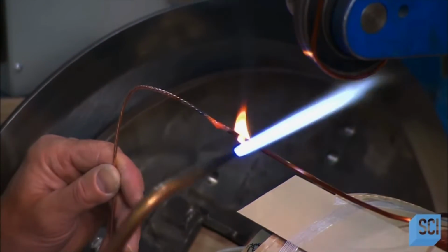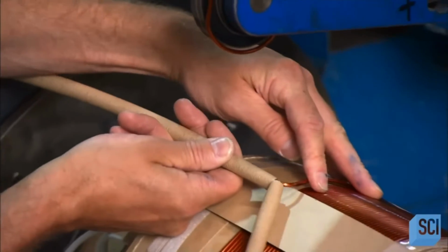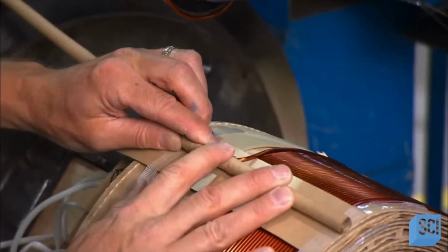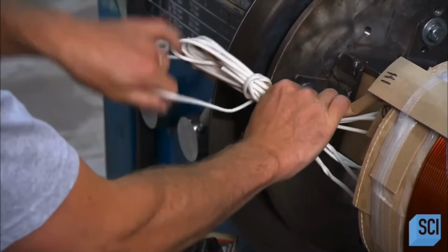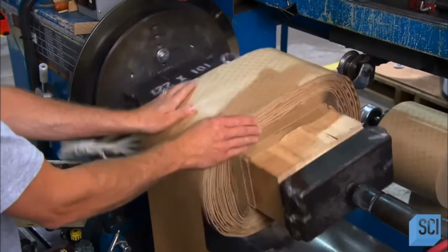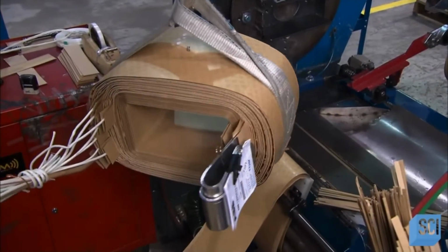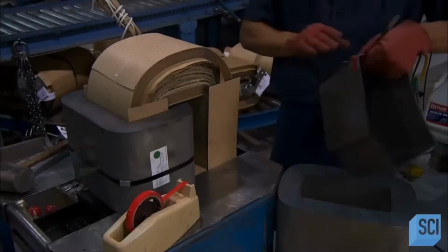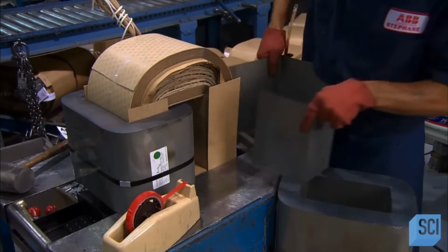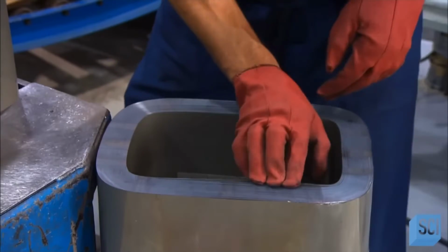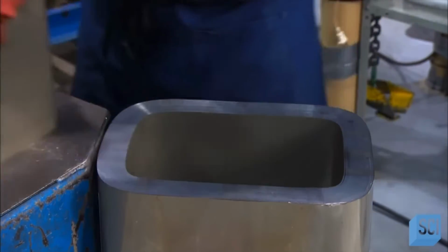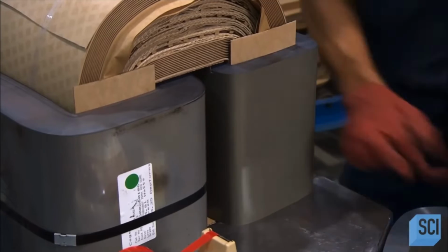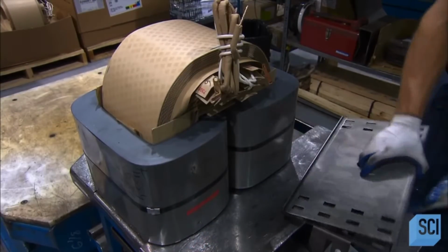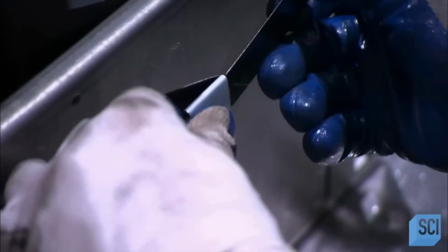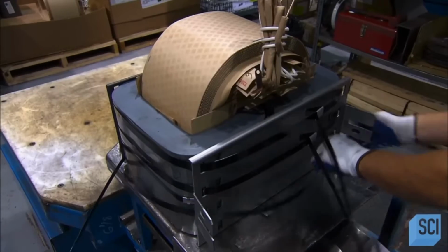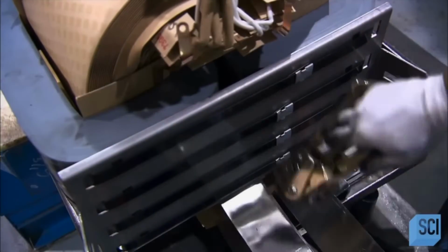Next, he welds on what's called the lead wire out, the wire that'll protrude from the transformer's cylinder, and attaches vinyl-coated wires that'll connect to different voltages out of the transformer. This completed unit is called the coil. Now, using electrical steel, workers build the transformer's other main component, called the core. The coil and core are tightly secured together with metal strapping, which will help to fix the assembly in the tank.